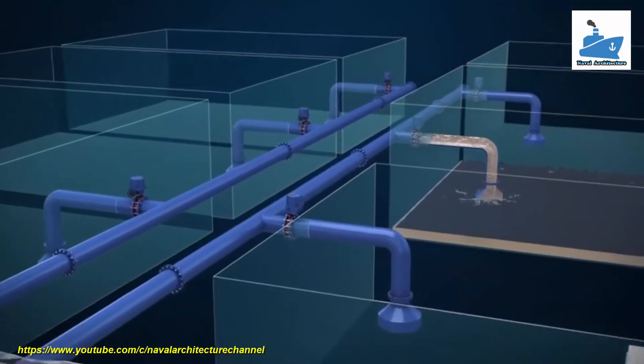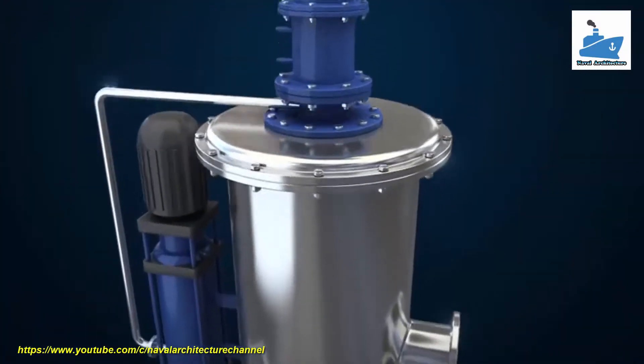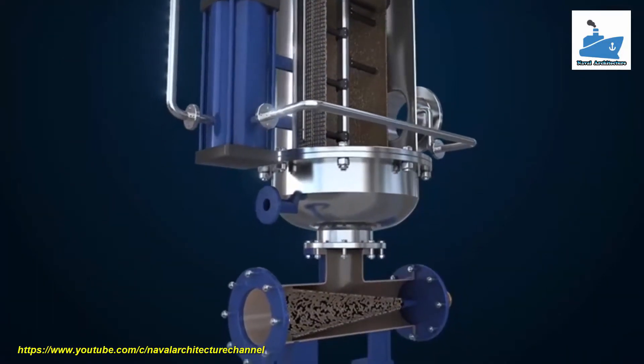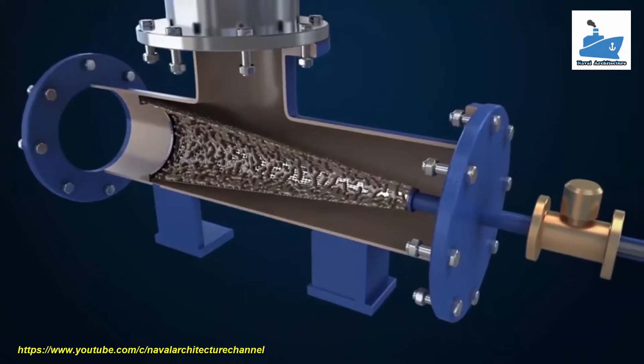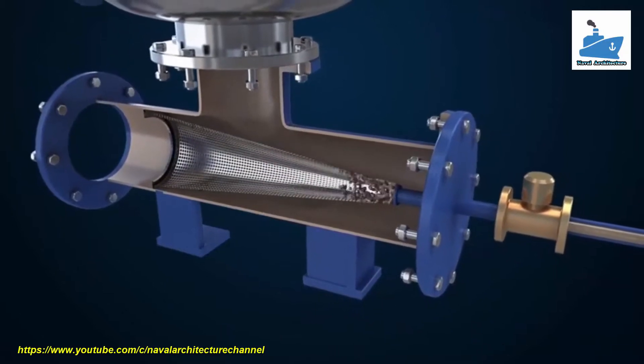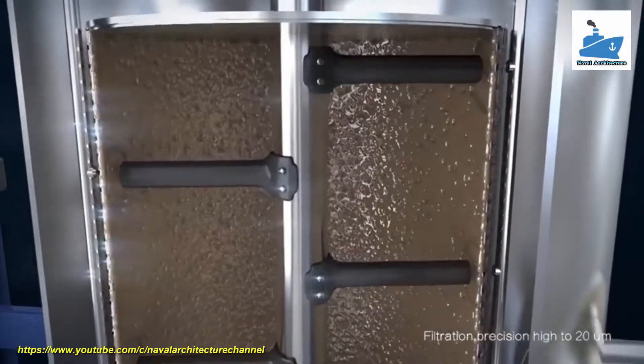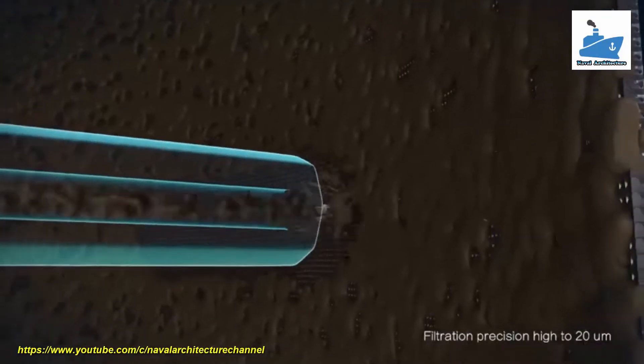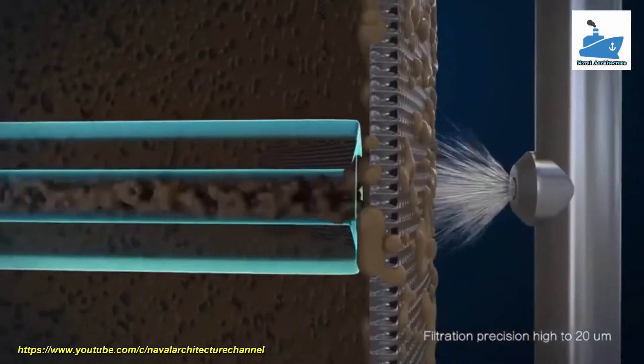Finally, seawater is pumped into the ballast tank. For the filter, when the differential pressure reaches the set value, the system will back-flush automatically and use 20-bar high-pressure water to flush the filter, so it can run efficiently in any water condition.